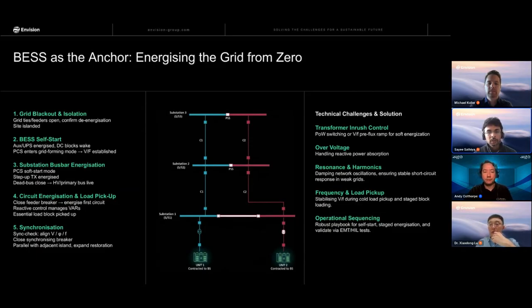That's when NISO will instruct us to perform the restoration services. Before NISO instructs us to perform the restoration, the first thing we need to ensure is that we have sufficient backup supply to feed all our critical loads in the AC, basically the PCS and the batteries. And it's not only about the PCS and batteries; we also have many auxiliary systems and switchgears and control systems, the plant EMS, SCADA. All these are very critical for us to perform the black start or self start. Once we have the backup auxiliary supplies for all the PCS and all the critical equipment, we wait for the instruction from NISO, and then we perform the black start.